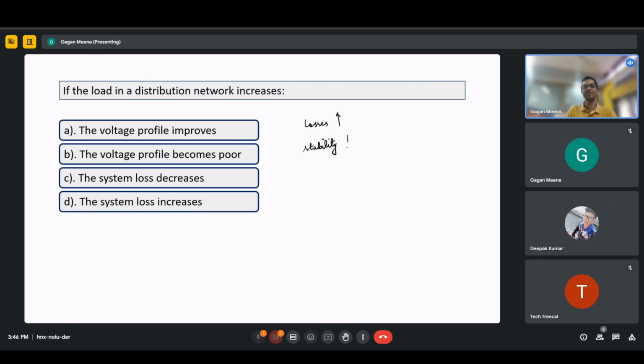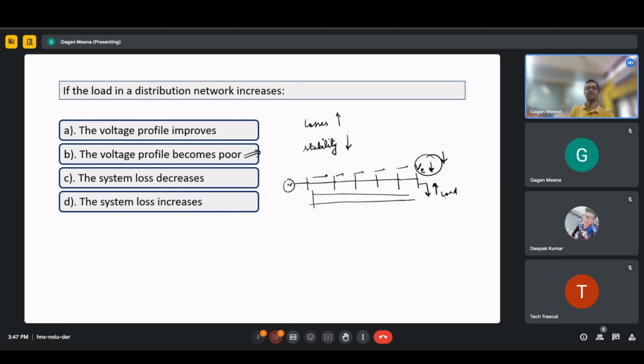So the voltage profile will become poor. If we consider the radial system, the load is at the far end of the distribution system. If the load here increases, losses will increase and the voltage at that end will reduce. The more the load increases, the more this voltage reduces, affecting the voltage profile. So voltage at the substation will be maximum, and as we move along the feeder, the voltage drops, and increasing the load further reduces that voltage.